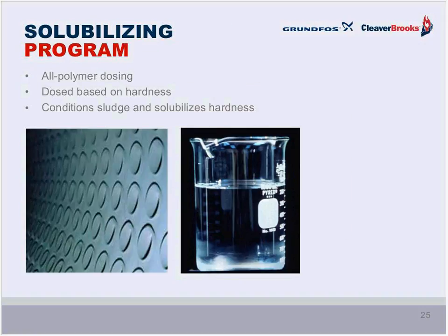And then what they call the solubilizing program, which uses an all-polymer chemical agent. Unlike the others, this treatment solubilizes the scale-forming minerals rather than sequestering them, and this actually cuts down on the amount of continuous blowdown required.